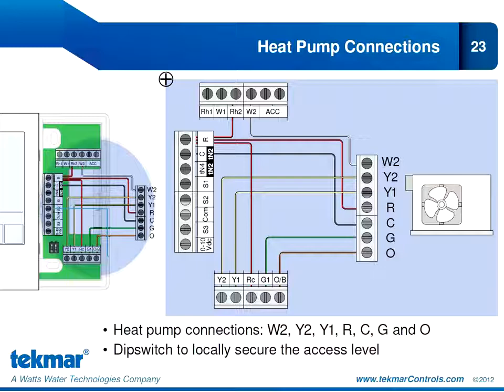These are the heat pump connections, and we wanted to show you this slide to see how easy it is to install the 557, how easy the connections are to the heat pump. These are your standard heat pump connections. W2 for backup, Y1 and Y2 for your compressor stages, G for fan control, O for the reversing valve, which would be energized for cooling, and R and C for 24-volt power.